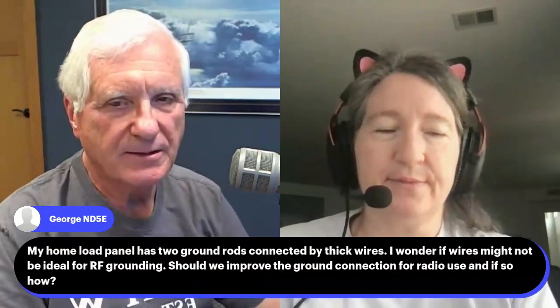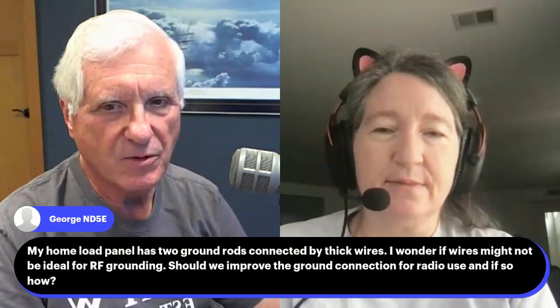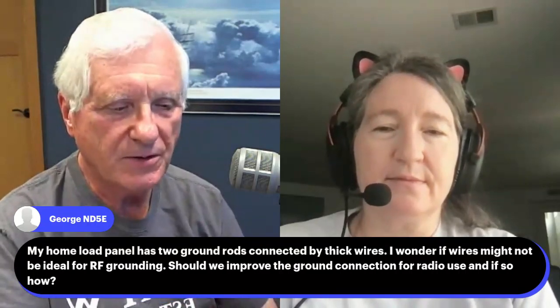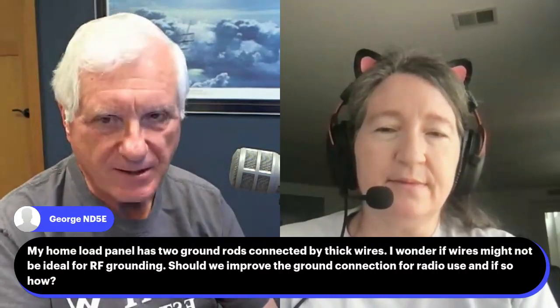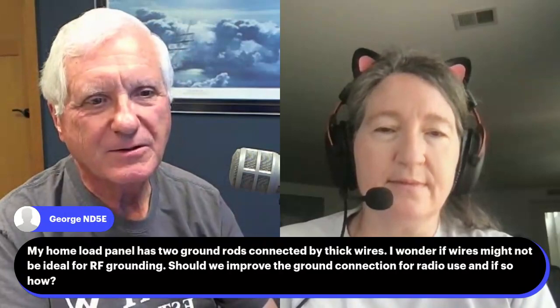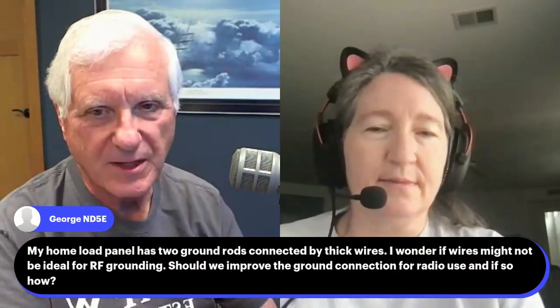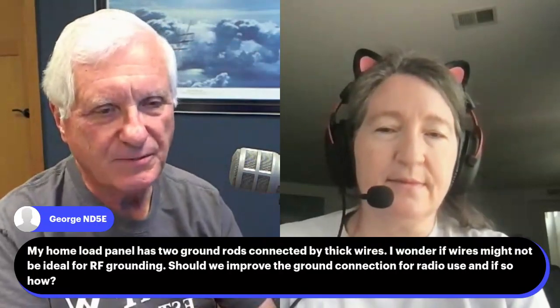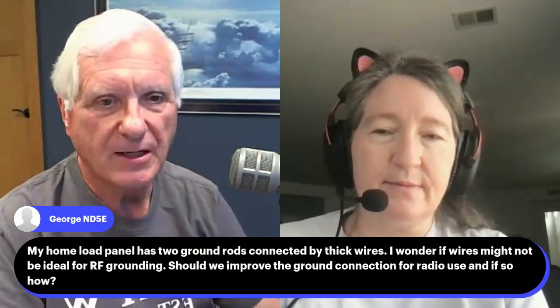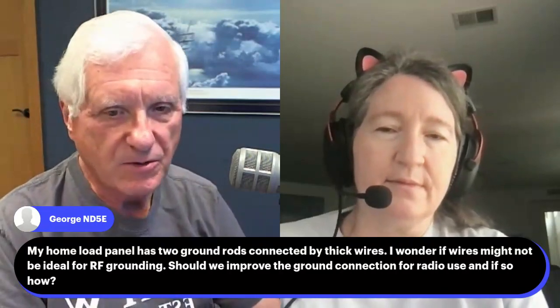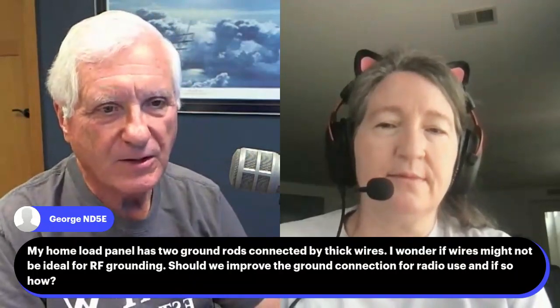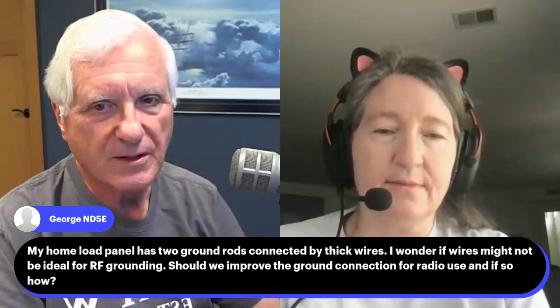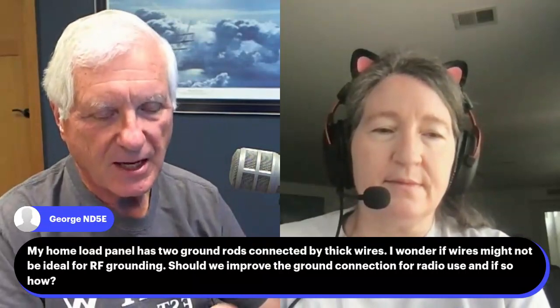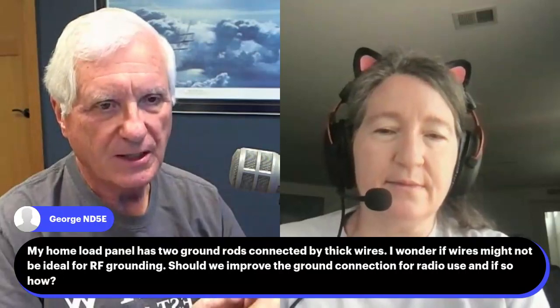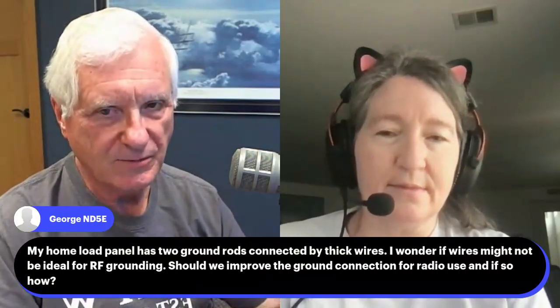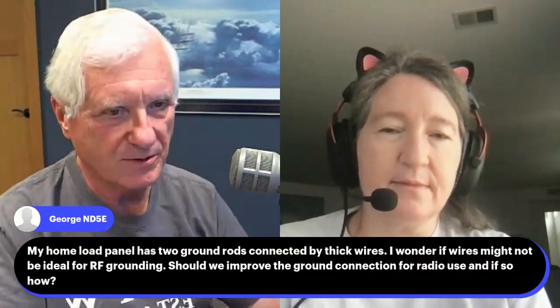In radio broadcast, surface area on a conductor is important. When we use number 6 ground wires, I mention stranded because there's more surface area on the individual strands. Even if they're touching each other, it doesn't matter as long as there's exposed surface. So in my mind, I get about twice the grounding capability out of stranded wire. Number 6 is pretty standard. Now, two ground rods, well, four is better, and they all tie to the same single point ground where your electrical service entrance is. That's the one and only place where neutral and ground are connected together. All subsequent panels have separate ground and neutrals.